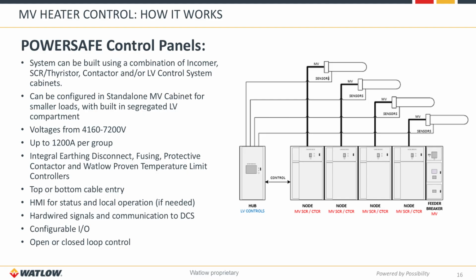If you need larger than that, we can do multiple groups of cabinets that are set up, so you can get up to 2400, 3600, whatever the case may be for the size of system that you have. Each cabinet has integral earthing disconnects associated with it, fusing, protective contactors, and Watlow's proven temperature limit controllers to ensure that the thermocouples that are embedded inside of these heaters are fed back to the system and any over temperature condition is taken care of adequately.